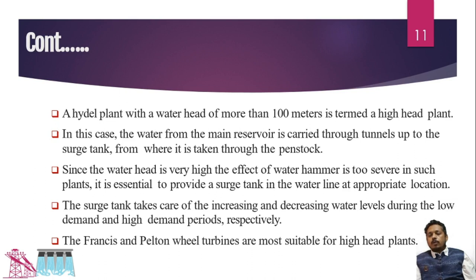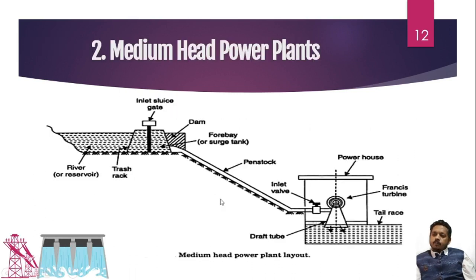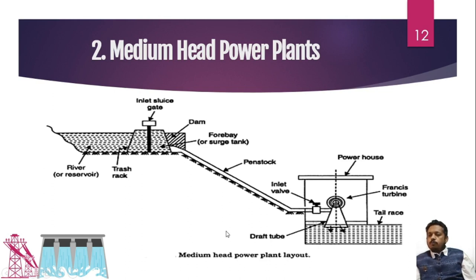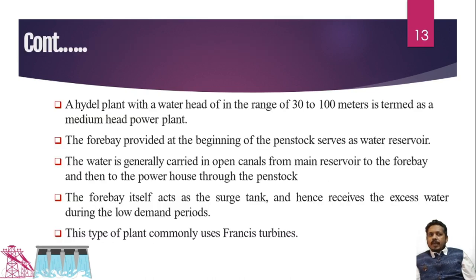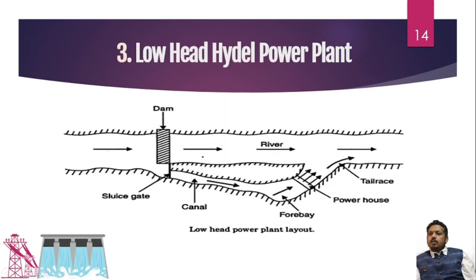In the medium head power plant, the head is 30 to 100 meters. Most things are similar to the high head plant, but the surge tank required is smaller. In medium head plants, a forebay — a facility that can flow excess water through another channel or tunnel — can act as the surge tank. Since the speed is a little less, a Francis turbine is used in this type of power plant.